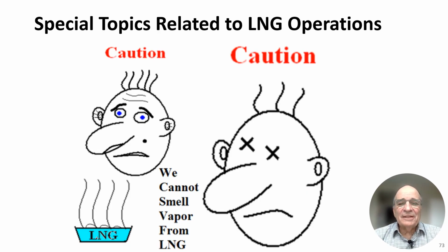Special topics related to LNG operation, a major caution. Nitrogen and also LNG vapors are odorless. So you cannot tell if you're in an oxygen deficient environment unless you're measuring for oxygen. So it's something to keep in mind. We don't often deal with vapor in a confined space or large amounts of vapor in an open space, and we may not realize that we are in an oxygen deficient environment if we have an LNG spill or if we have a large nitrogen release.